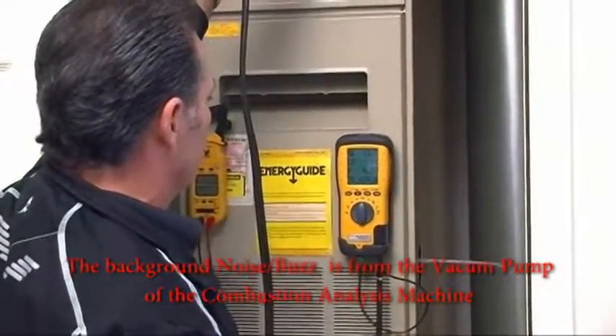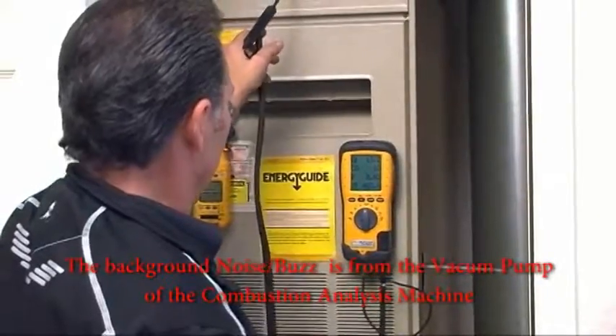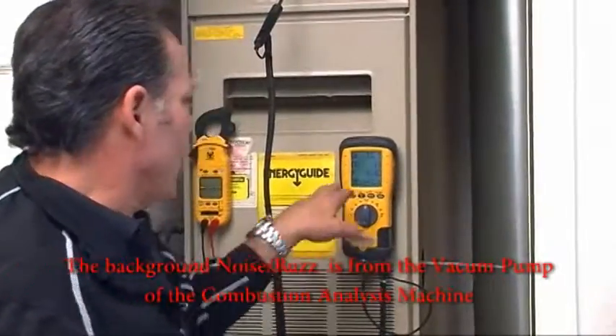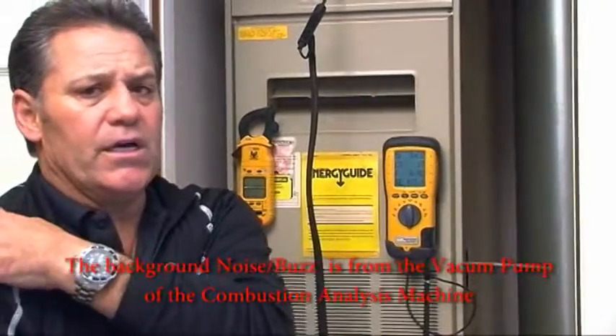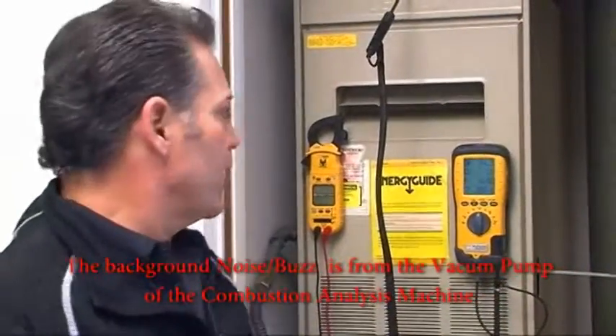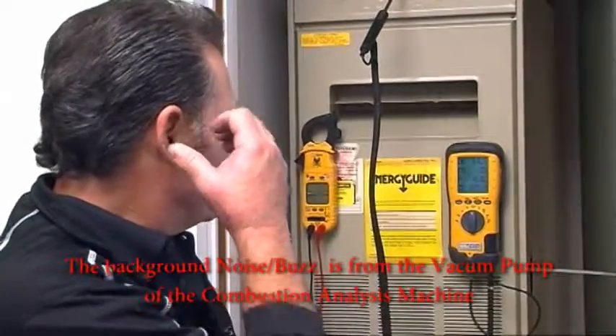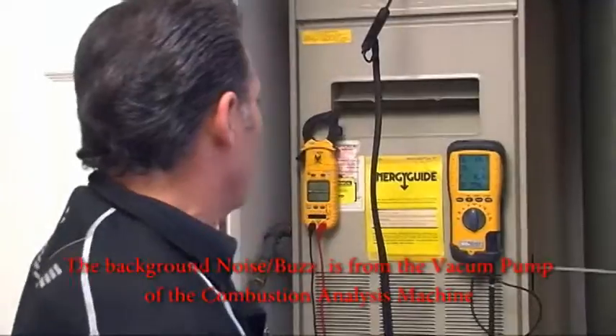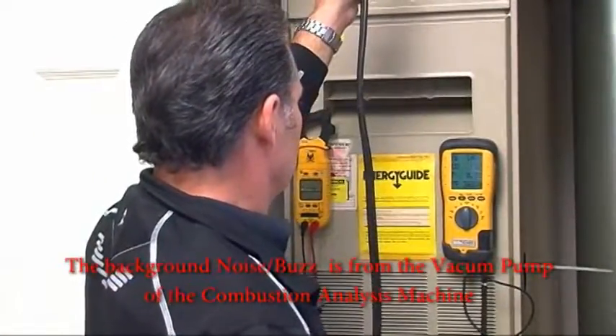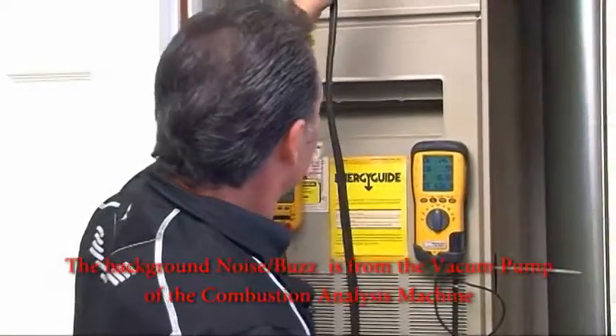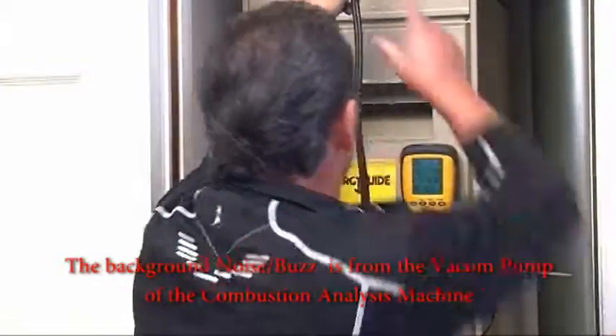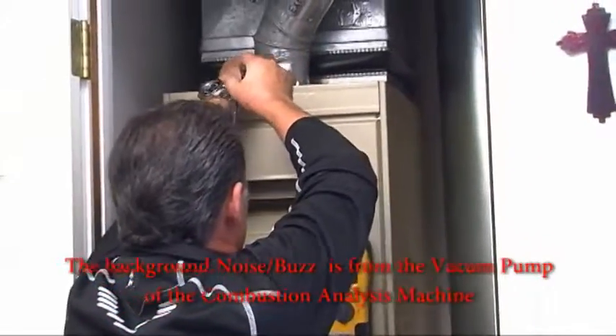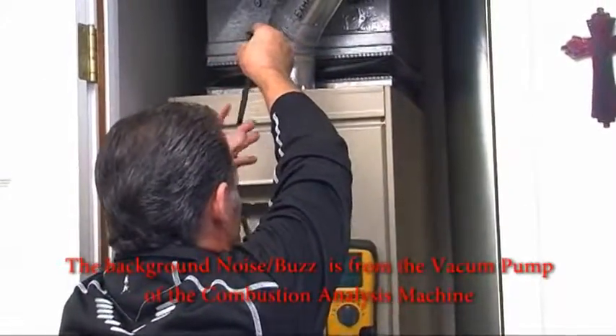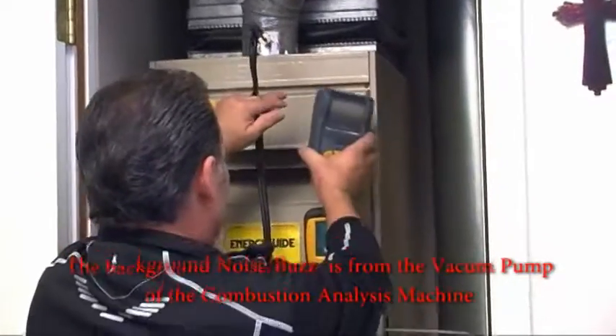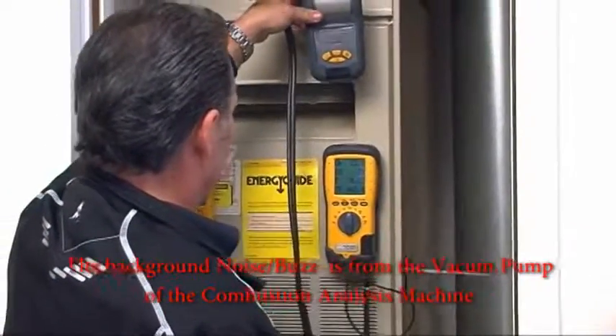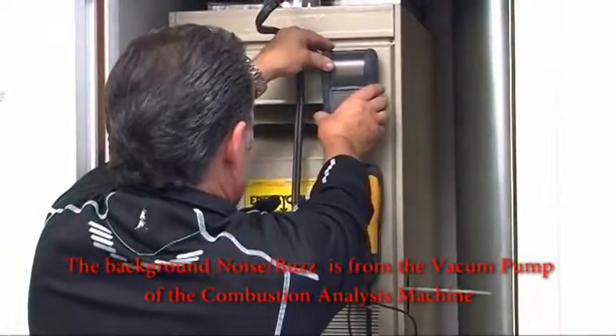We did some adjustments on this earlier to make sure everything was good. An 80% furnace should be in the area of 400 or above on the flue temperature. 350 to 375 is going to be your low end. So let's see what we have. Let me push my keeper on my probe in there a little more so it steadies it. Okay. So now I'm going to go ahead and do my printout on my test, as soon as it settles down some.